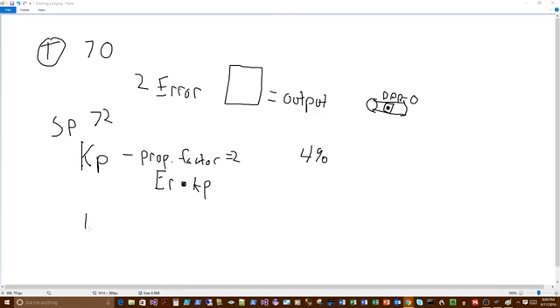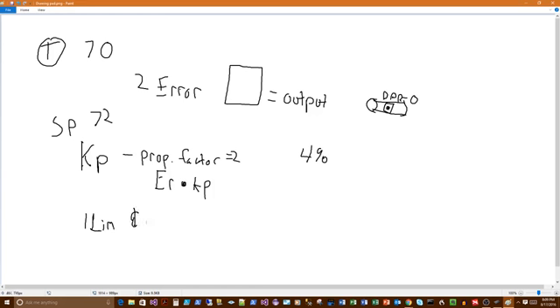And you're going to have ILim and Imax. So these are going to be your settings. So your ILim is going to be how much the integral can increase each pass. And basically what's going to happen is you're going to have this time factor. So let's say we're going to use an ILim of 1.5, and we'll say that our Imax is 60. We're just going to say that. So each time your loop runs, and a loop will typically run every second.